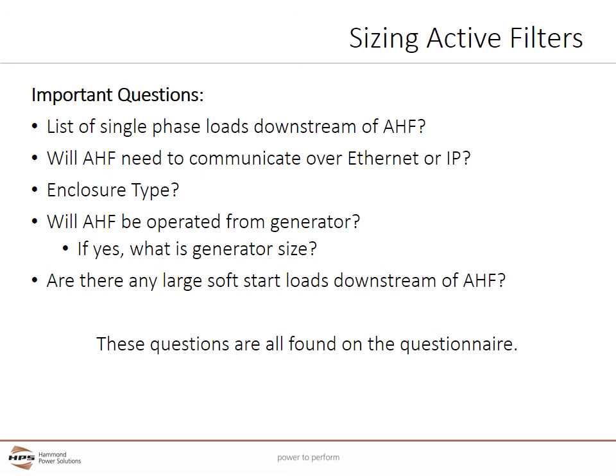Other important questions include: Is there a list of single-phase loads downstream of the active harmonic filter? Will the active harmonic filter need to communicate over Ethernet or IP? What is the enclosure type of the active harmonic filter? Will the active harmonic filter be operated from a generator, and if yes, what is the generator's size? Finally, are there any large soft-start loads, also known as reduced voltage starters, that are downstream of the active harmonic filter?